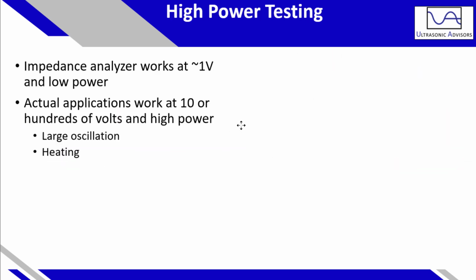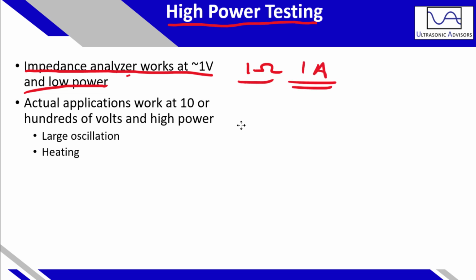In this slide, I'm going to give a brief overview of high power testing of ultrasonic transducers. The impedance analyzer works at 1 volt, and it can only provide low power. So even if you had a 1 ohm resonance impedance, you will not be able to provide 1 amp from your impedance analyzer. The trade-off is that by using low voltage and low power, you get an extreme amount of consistency, and that is where this device shines, and why it's a basic analysis parameter, because in order to do better characterization, we need to obey and follow linearity.